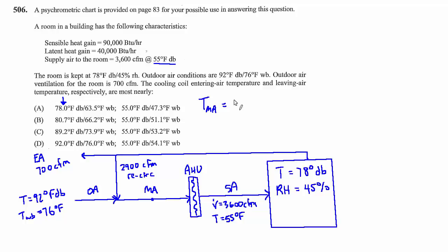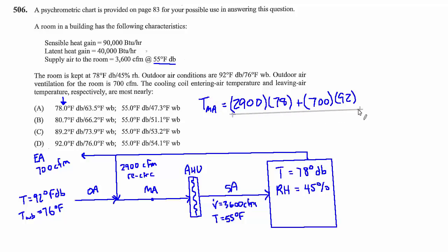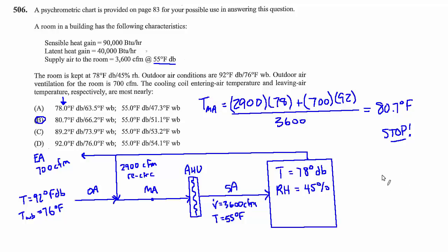The mixed air dry bulb temperature is calculated by mixing the recirculated air and the outside air: (2,900 CFM × 78°F + 700 CFM × 92°F) ÷ 3,600 CFM total = 80.7 degrees Fahrenheit. This is consistent with answer choice B. In a test environment, you could stop here — you have the answer.